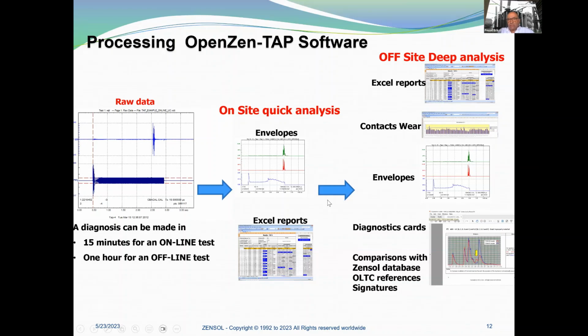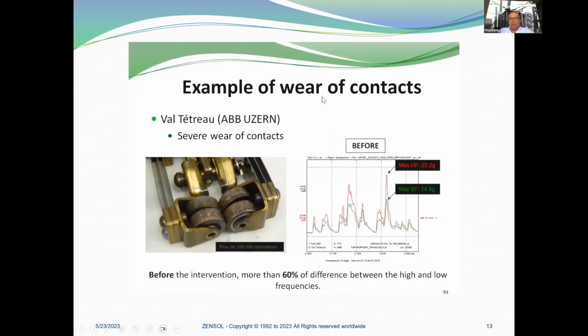And offsite deep analysis. Thanks to what we call the Excel report, which focuses on the transition time and the amplitude of the envelopes, we are able to detect contact wear. We analyze the envelope. We have diagnostic cards, and we are able to compare with our Zensol database of OLTC reference signatures. Here we have an example of worn contacts. This was done at Hydro-Québec.